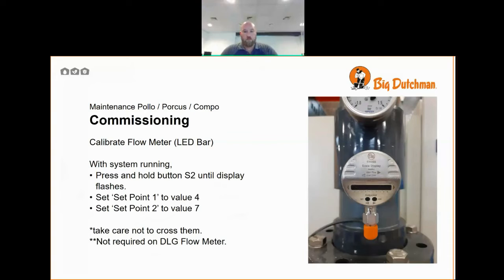We need to calibrate the flow meter, as we call it, the LED bar. With the system running, we press and hold S2 until the display flashes. The LED on the very right hand side will stay on solid and then start to flash. This will tell the sensor that it is now reading 100%. We need to set point 1 to value 4, set point 2 to value 7. Take care not to cross them over. This is not required for the DLG certified air scrubbers, as we use a different flow meter.